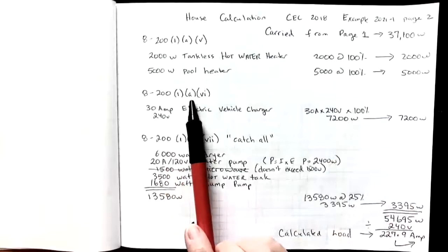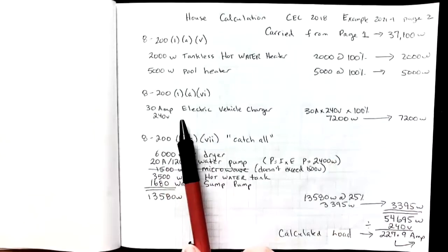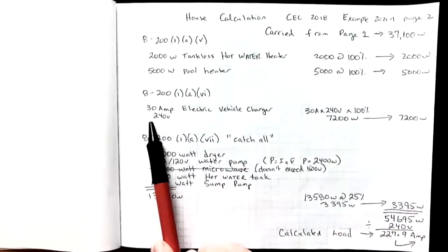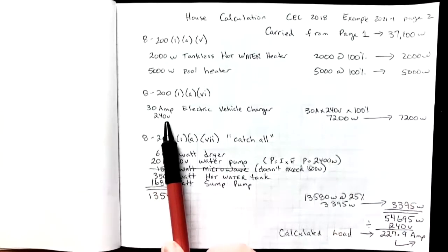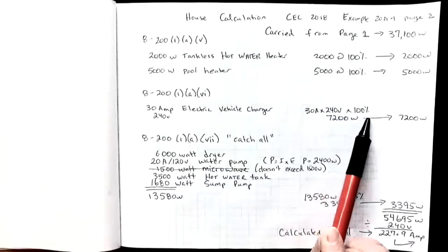Rule 8-200(1)(a)(6) is where we find the demand information for an electric vehicle charger. This was a 30 amp charger times 240 volts will give me my watts, and that would be 7,200 watts. We take that at 100% towards the main service.